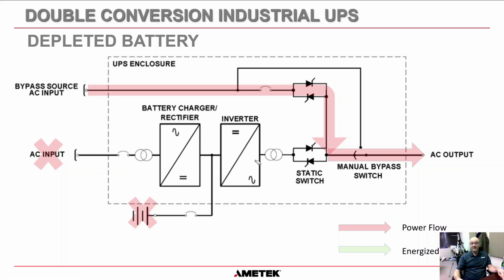And what happens is, first of all, the UPS itself says, okay, my battery has got too low, I need to transfer to bypass supply. So it turns this bypass static switch on, and only when that switch is on, it will then turn the inverter static switch off. Okay? And then as soon as it has done this, it says, now I am going to trip the battery input breaker to prevent the battery from feeding power into the inverter. Hopefully that makes sense, what happens when the battery discharges too far.